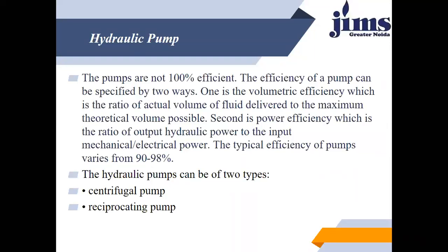The hydrostatic or positive displacement pump ejects a fixed quantity of fluid. I already discussed in the previous class that they can only eject a fixed quantity of fluid per revolution of the pump shaft. So the pump outlet flow is constant and is not dependent on the system pressure. These pumps are well suited for fluid power systems, and you are familiar with those.